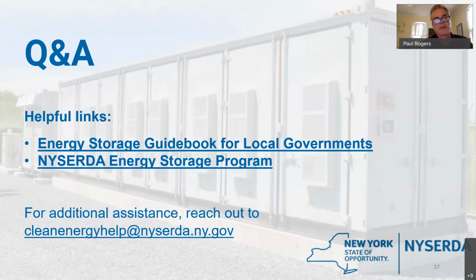Well, that really comes down to the comfort of the AHJ. In certain areas, they're going to request that you have to have it done in order to move forward, making sure you have this 9540A testing done. But again, it's really up to the AHJ. Are they going to put these things in there when they haven't proven themselves? Well, maybe I shouldn't say they haven't proven themselves to be safe, because they may be very safe. Maybe they just haven't gone through the test. But they kind of try to keep everything uniform, having the exact same test for all the different energy storage systems out there. And what comes out as a result of that test is really going to show whether you have the proper safety features in place, separation distances, or whatever it may be.